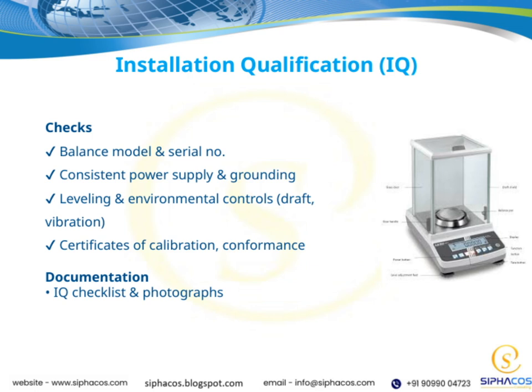Then, we focus on leveling and environmental controls. It's important to check that the equipment is properly leveled and that environmental factors like draft and vibration are minimized, as these can impact performance. Lastly, we review the certificates of calibration and conformance to ensure the equipment has been properly calibrated and meets all required standards. Moving on to documentation, we gather the IQ checklist and photographs. These serve as essential proof that everything was set up correctly and according to plan.